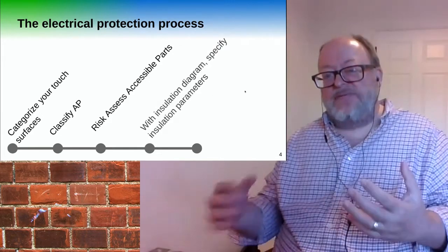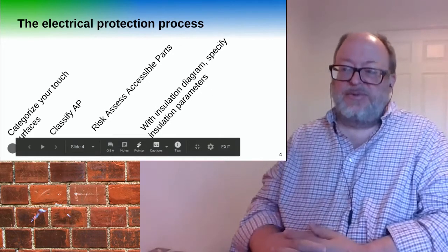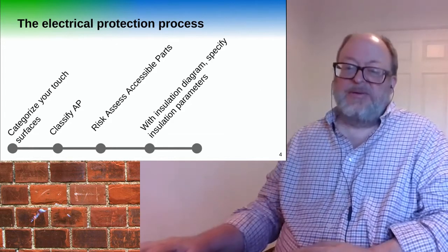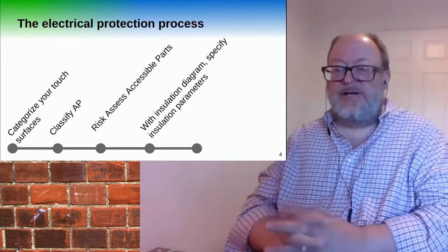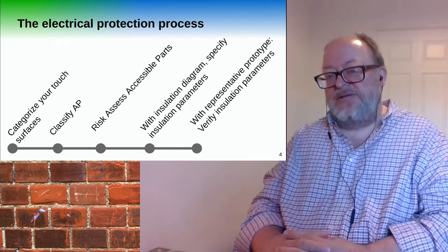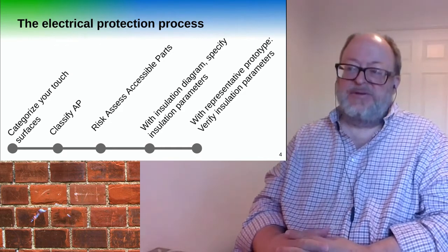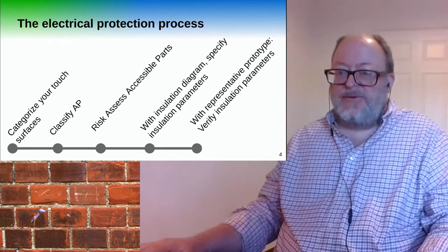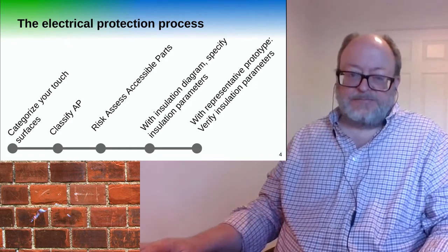And then once we have that information, we're going to put together an insulation diagram. That'll specify insulation parameters. And then you've got your test plan. Those insulation parameters will need to be verified after you've built the prototype. So let's see if we can do this.